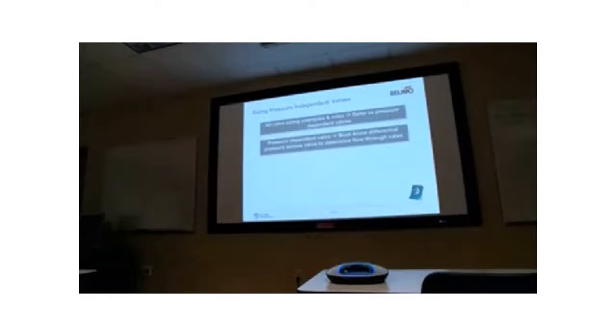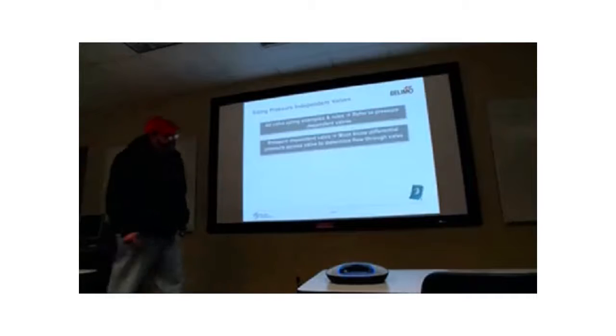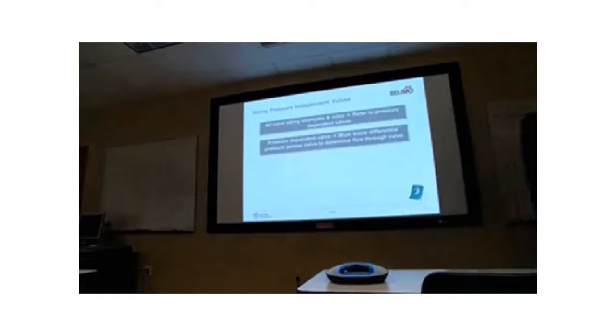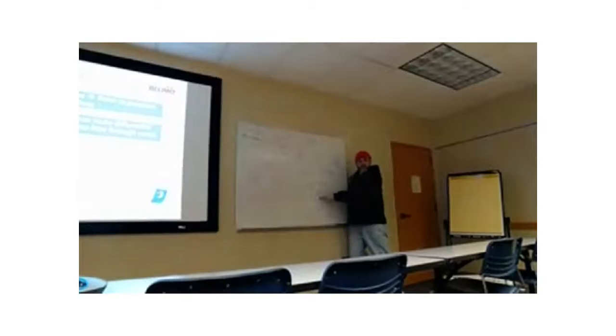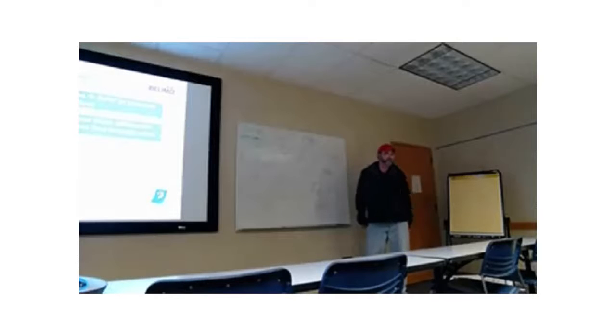Now on the water side, we do pressure independence a couple different ways. We do it the way I just explained. We get a flow meter, we get a valve. Remember that closed loop? Is that still on the board here? Yeah, so if you want to go back to this, we have a valve that works to control flow just like this. That is to say, we measure the flow, we have some control functionality. This actuator is on what? This is actually the control valve itself. And we control the flow independent of pressure. That's one way to do it.